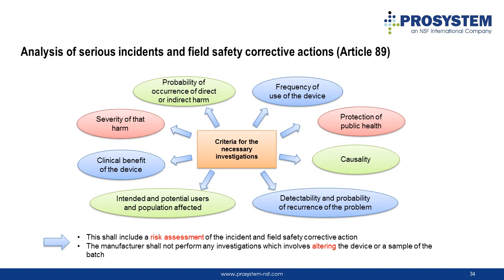After reporting, manufacturers are required to conduct investigations on serious incidents of the concerned medical device. The criteria for the necessary investigations were also defined in the MDR, such as the severity of harm, frequency of use of the device, intended and potential users, and so on. The analysis shall include risk assessment and field safety corrective action. Manufacturers must work with competent authorities and notified bodies regarding the investigations.